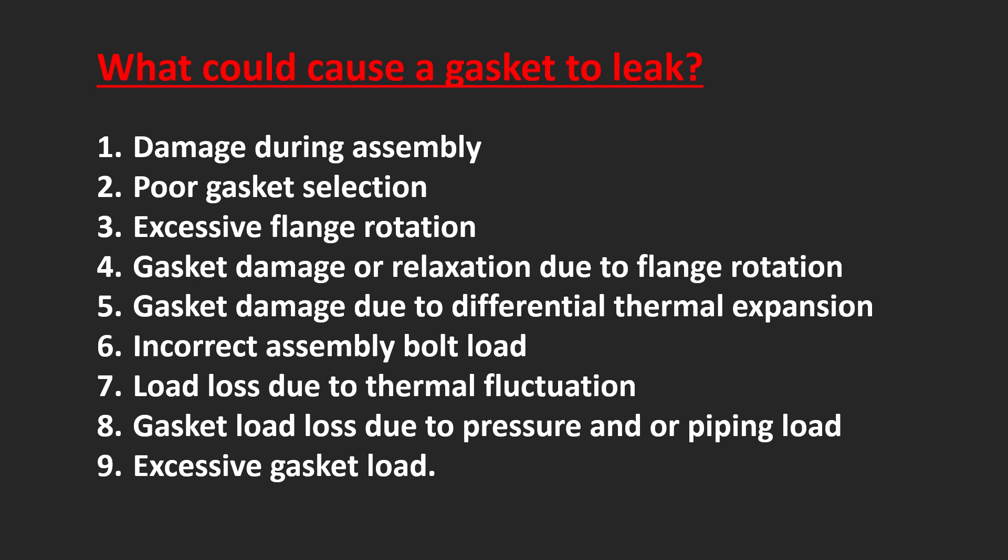What could cause a gasket to leak? Damage during assembly, poor gasket selection, excessive flange rotation, gasket damage or relaxation due to flange rotation, gasket damage due to differential thermal expansion, incorrect assembly, improper bolt load, load loss due to thermal fluctuation, gasket load loss due to pressure and/or piping load, and excessive gasket load.